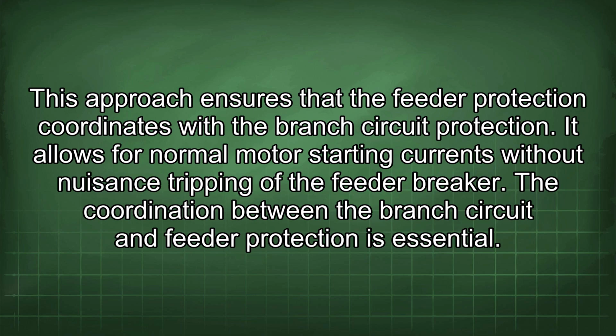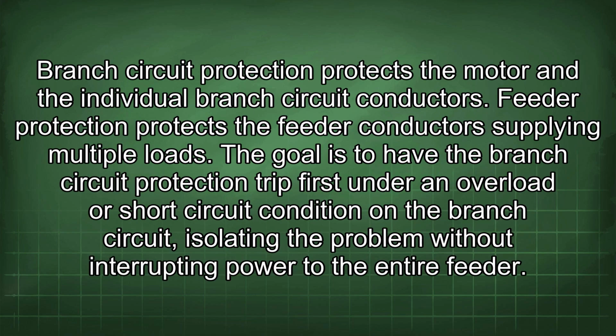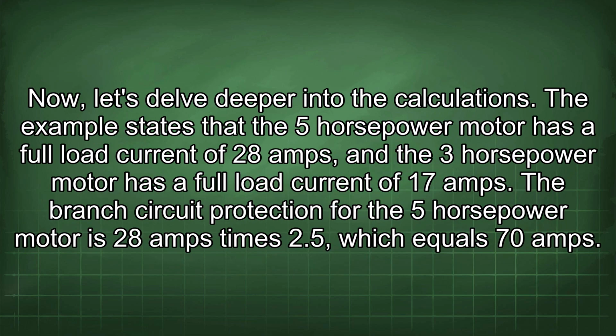The coordination between the branch circuit and feeder protection is essential. Branch circuit protection protects the motor and the individual branch circuit conductors. Feeder protection protects the feeder conductors supplying multiple loads. The goal is to have the branch circuit protection trip first under an overload or short circuit condition on the branch circuit, isolating the problem without interrupting power to the entire feeder. Now let's delve deeper into the calculations.